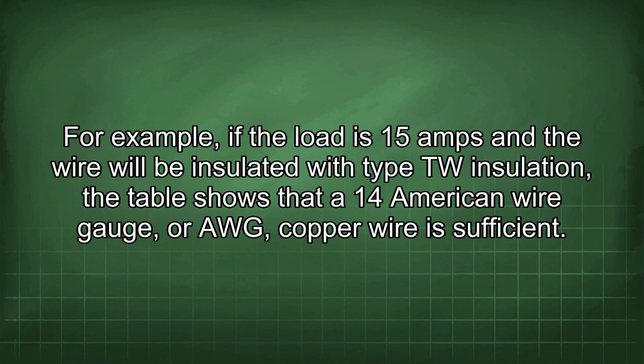For example, if the load is 15 amps and the wire will be insulated with type TW insulation, the table shows that a 14 American wire gauge, or AWG, copper wire is sufficient.